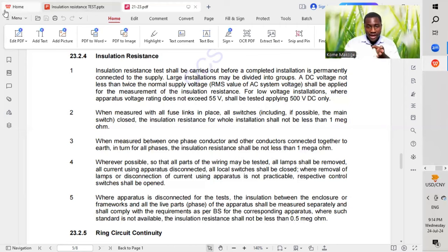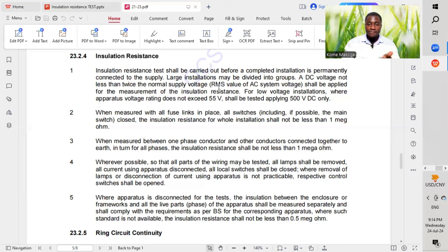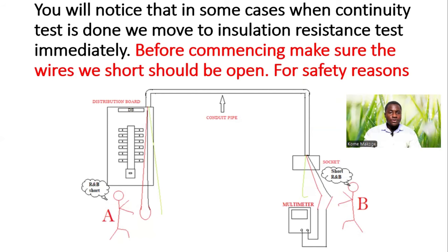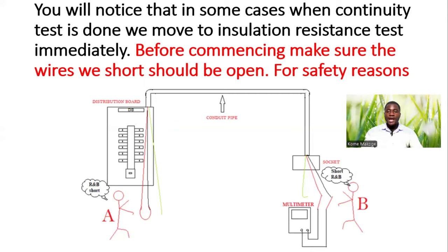So we get to understand how to carry out the test. The code tells us that a DC voltage, which is not less than twice the normal voltage, has to be applied, which will be injected by the insulation resistance tester. In some cases when continuity test is done, we move to insulation resistance test immediately. Once we are done with continuity test, we move immediately to carrying out insulation resistance test or mega test.